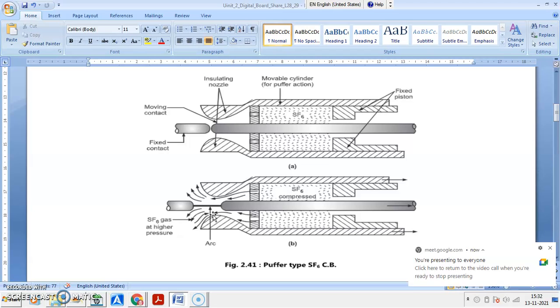Then, when fault occurs, the fault is sensed by the relay, sensed by the circuit breaker. Circuit breaker starts its opening operation by sensing the fault from relay by actuation of the trip circuit. The contacts get open. Now here, contact gets open means this entire cylinder moves back, direction is shown, this entire cylinder moves back.